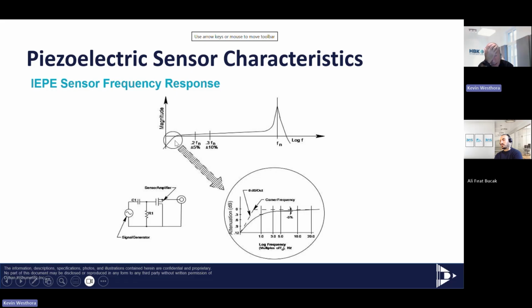So the two main things that you need to remember about IEPE sensors is, one, they're constant current powered, and two, they're AC coupled, right? So they could never measure a static measurement. They can't measure static pressure, static force, or static acceleration. They have a bleed off, and this is the bleed off called the discharge time constant, this low end roll off at your low end frequency.